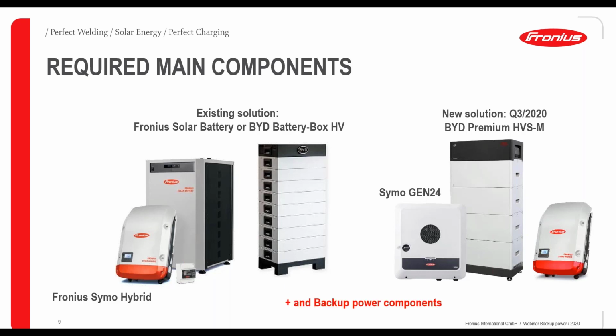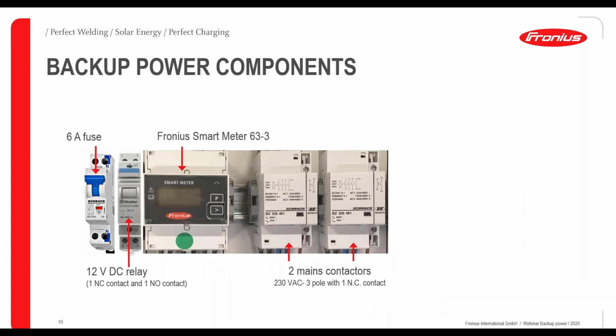And additionally, of course, we need the backup power components, so the contactors and relays which are required to switch over to backup power mode. And these components are as follows. The Fronius smart meter, the 6 amp fuse, a 12 volt DC relay, this kind of Finder relay with one normally closed contact and one normally open contact, and as well 2 main contactors, 230 volt AC, 3-pole or 4-pole with one contact normally closed. You just need to take care about the current, but it is usual standard in Europe to use 2 contactors.